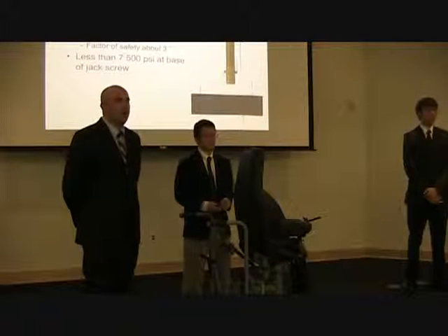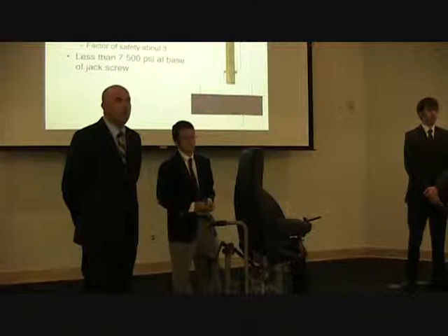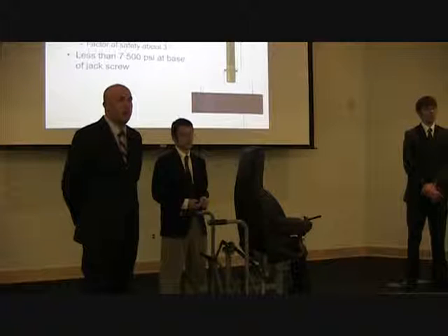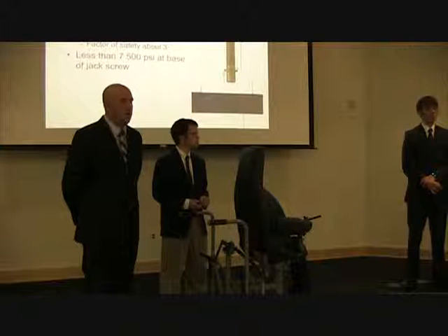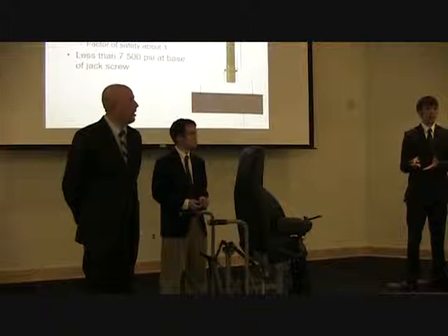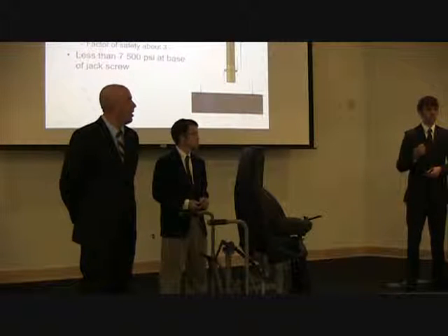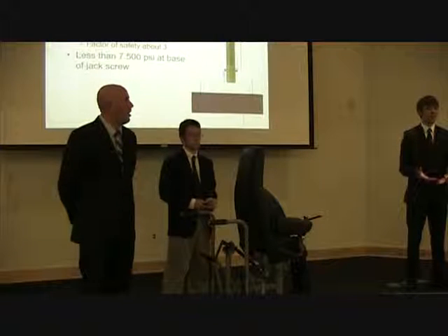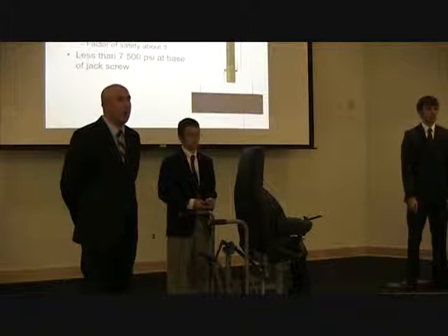You mentioned you passed the FDA test for the tilt, front and back. What does the test specify that you have to be able to withstand? Well, it's actually part of the 510(k), a form that you have to fill out and get approval from the FDA. Okay. And inside that form, you had to record the tilt angles. It wasn't like a max or min. You simply write it down. If you tilt it half a degree, you just have to put it down in there and let them know.